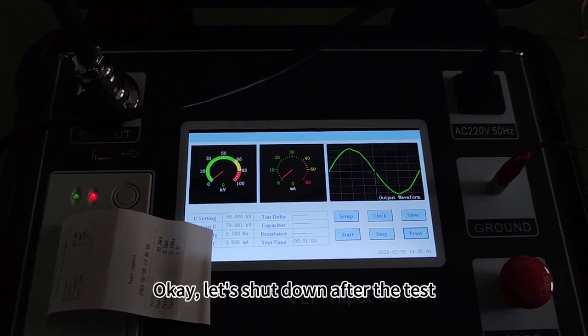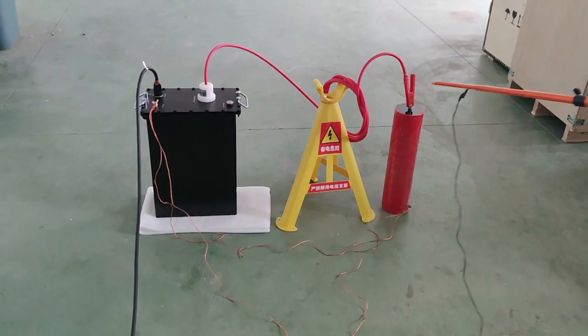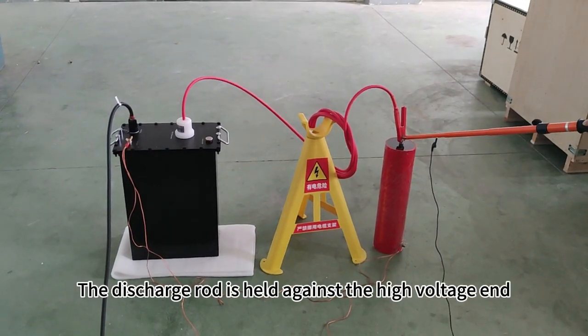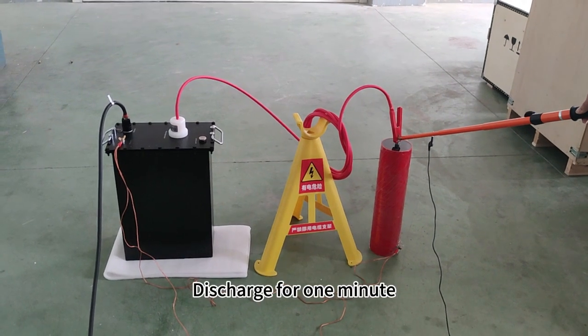Okay, let's shut down after the test. Power off. Next, discharge. The discharge rod is held against the high voltage end. Discharge for one minute.